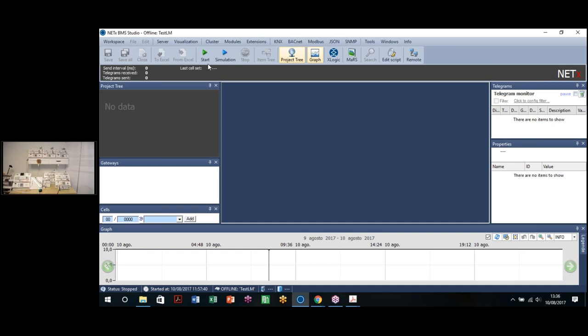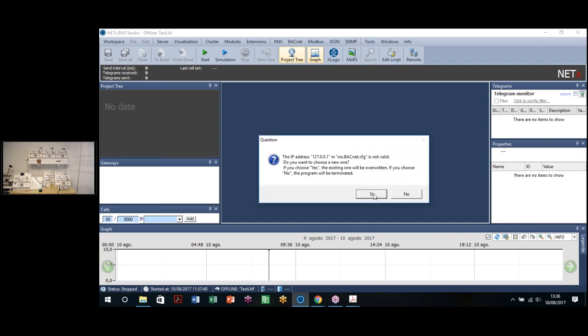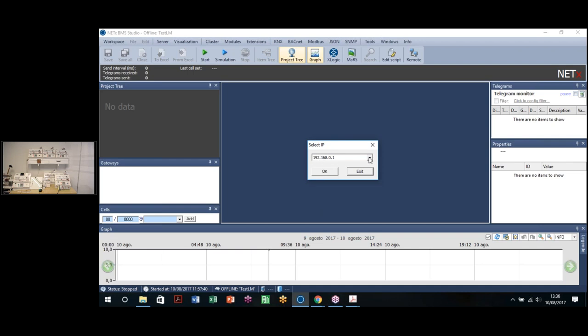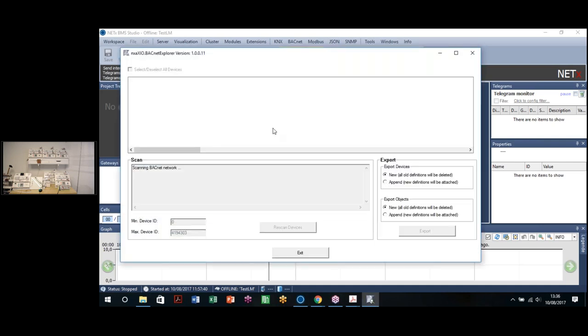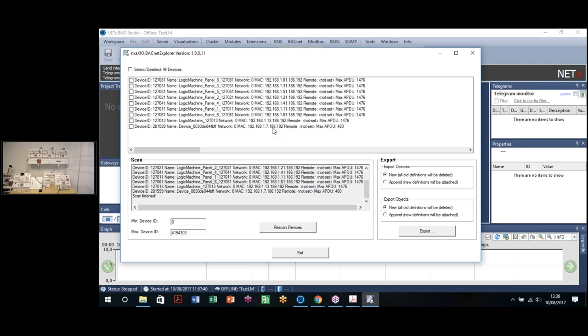So we stop the BMS and we have a BACnet explorer, so we can open. And it will check all the network. Yes, we are prompted about the IP address that we can use. Okay, exploring the network, very easy. It should show all the BACnet devices that we have, and all our LogicMachine devices are BACnet, but also we have a WAGO device here.